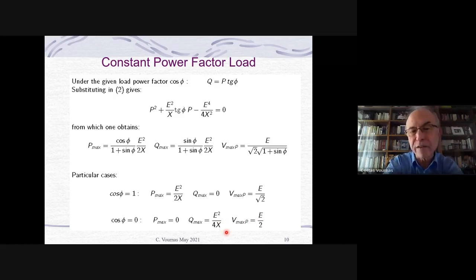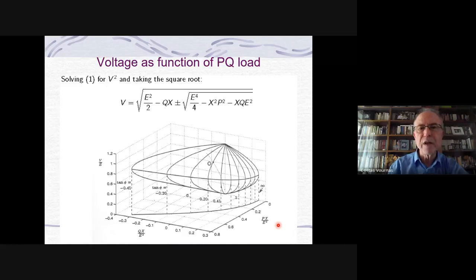So you see, when I try, in a lossless AC system, to transfer Q, reactive power, then the limit is exactly the same as in the DC system with only resistance. So it is 0.25 times the short circuit power. And the voltage where I have the maximum power transfer is 1/2 of my feeding voltage. So these are some simple formulas. You can plot them in many ways.